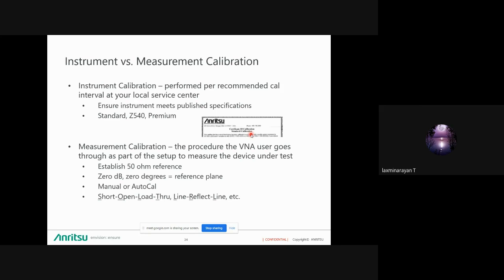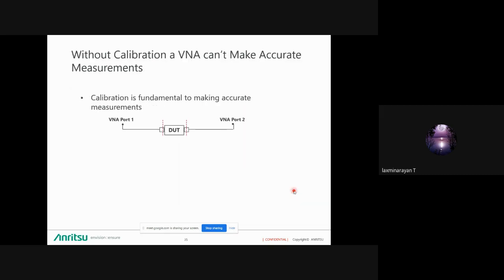There are different types of calibration methods, related to the device, like coaxial, waveguide, microstrip, or material measurement. So depending on the DUT, we can do different types of calibration. This is SOLT calibration, which is used for coaxial. LRL is also used for coaxial, and there are SSLT and SSST for waveguide. Depending on the type of the DUT, we can change the calibration types. This is the mechanical calibration kit in a wooden box, which has different standards included in the calibration kit. So this is how it works.